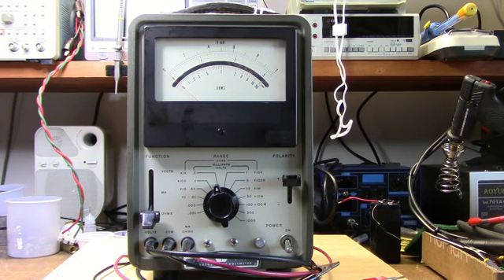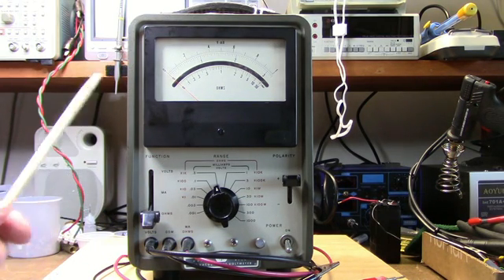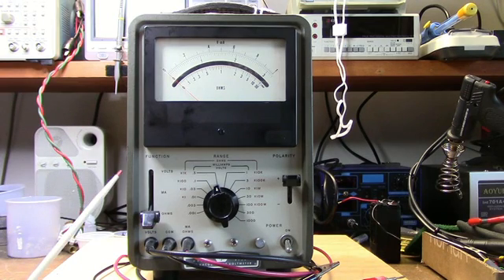Another thing nice about this instrument is the inputs are isolated from the chassis of the instrument, which is really nice. It eliminates ground loops and is a lot more functional than the meters that have the case actually connected to ground. And this does have a three wire line cord coming in, so the case is grounded to the line.